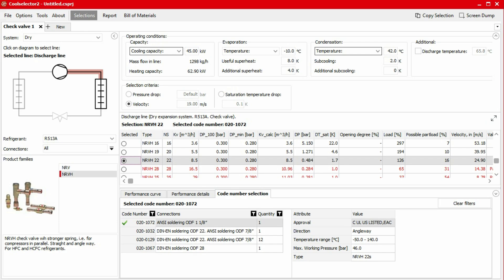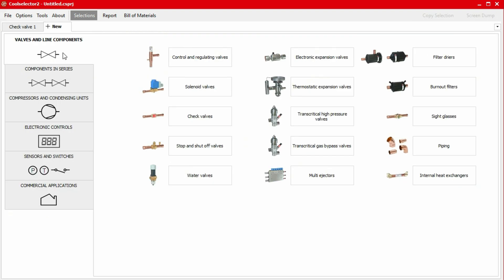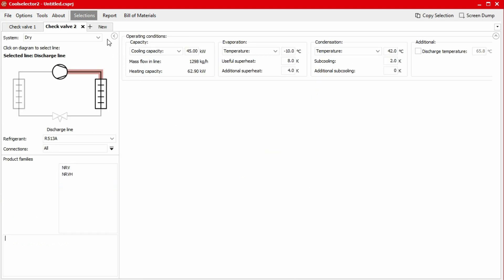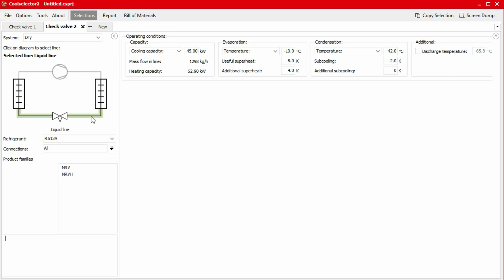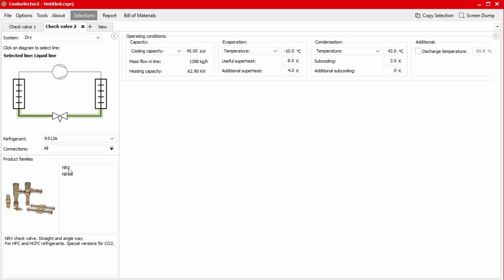If we want to add a check valve to the same system in the liquid line, we can click on the new tab and then select the valves and line components tab and then select check valves. Notice that CoolSelector has kept the same system, refrigerant, and operating conditions. As this check valve is for the liquid line, we will select the liquid line from the system schematic. In the product family section, we again have the option for the NRV or the NRV-H check valve. As there are little to no vibrations or gas pulsations in the liquid line, we can therefore select a standard NRV check valve.